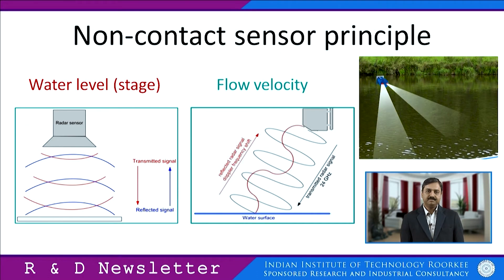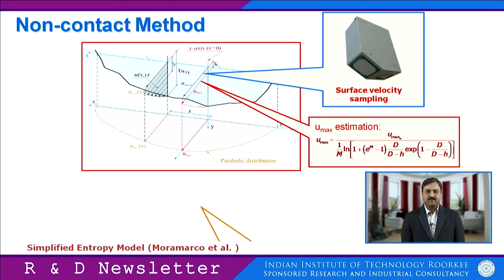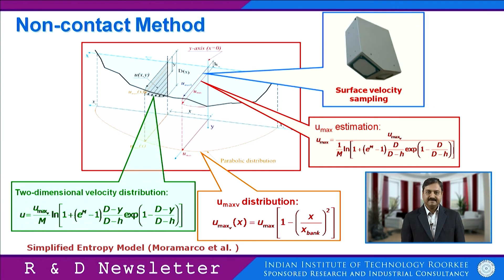Under this project we will be deploying non-contact sensors which are working on the radar principle. The water level would be measured using the radar principle, and the velocity of the flow would be measured by measuring the shift in the radar frequency. The sensor will first sample the velocity, and from there, using entropy principles, we will be estimating the maximum flow velocity and the horizontal velocity profile would also be estimated.